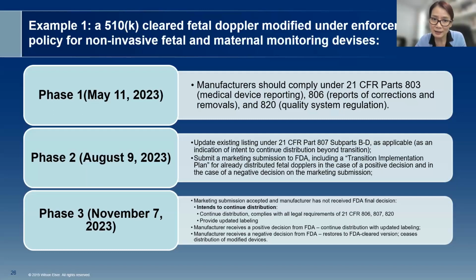Example number 1 is a 510(k) cleared fetal Doppler modified under an enforcement policy. It was cleared before COVID, and after COVID started, it got modified, which happened a lot. A portable device was modified into a remote device, which happened very often during COVID. So when phase 1 starts after May 11, the manufacturers should start complying with all of these regular FDA regulations. After phase 2 starts, the manufacturer should make a marketing submission as early as possible so the FDA has time to accept it before the end of phase 2. And that marketing submission needs to include a transition implementation plan if you intend to continue marketing your products after the transition.